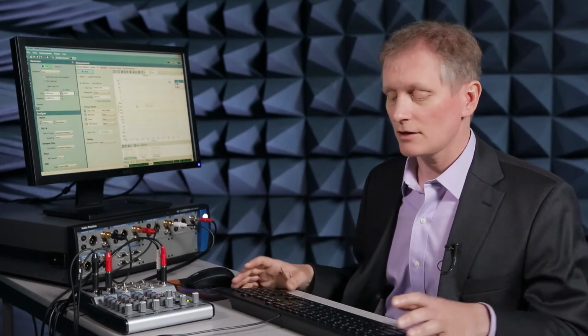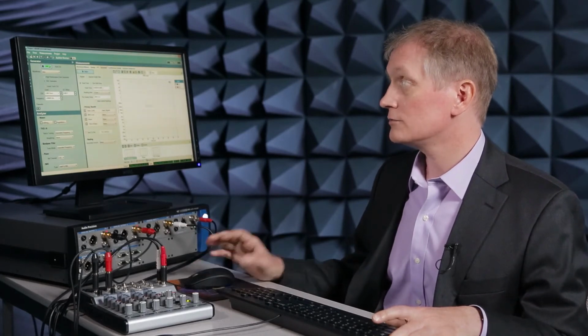Now, one of the features we've added for bench mode is a thing called recorder. And I'm going to show you that here. Let me flip over to the recorder tool. What this allows you to do is just record parameters of your device over time. So any particular parameter that you're interested in, RMS level, gain, THD, things like that, you can record them as they vary over time. The way I've set this up, I'm going to record for 10 seconds, but that can be as long as you like.